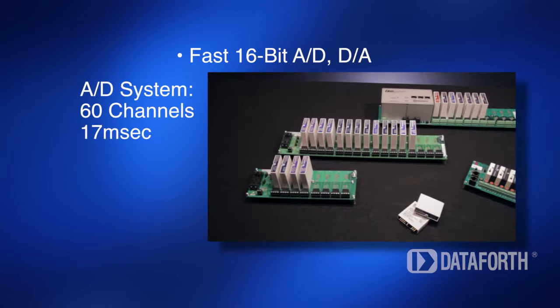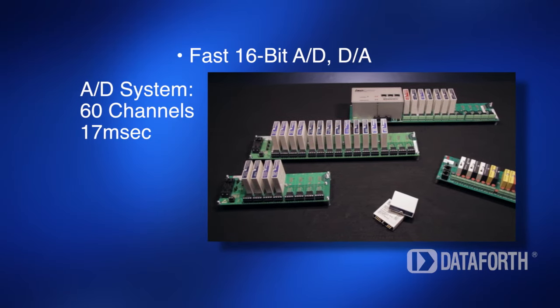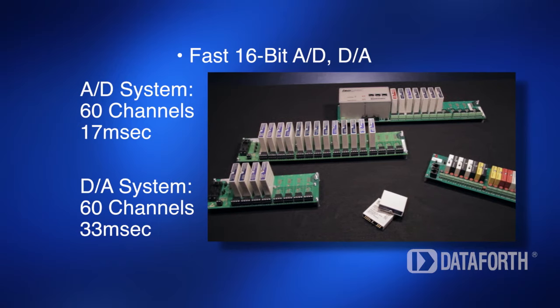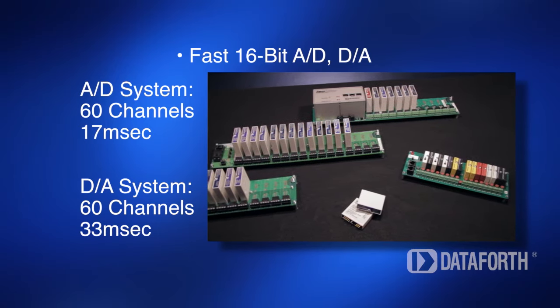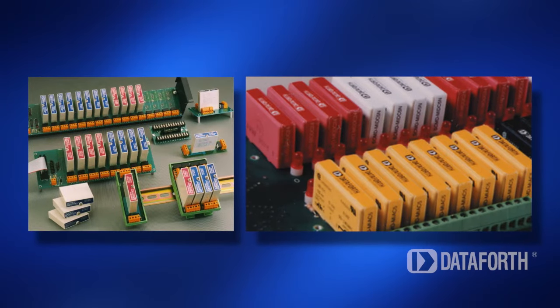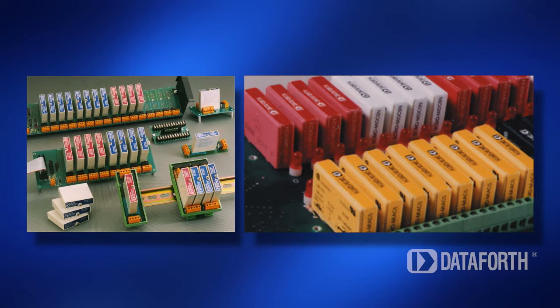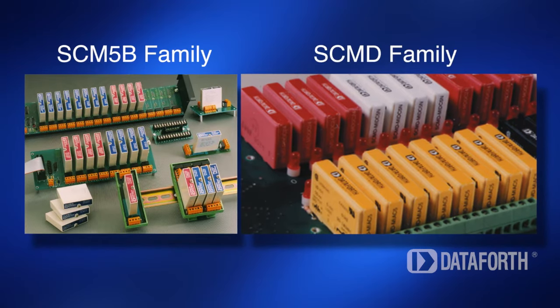The analog-to-digital system can convert a maximum 60-channel configuration in 17 milliseconds. The digital-to-analog converter can write a 60-channel configuration in 33 milliseconds. The signal conditioners used to build an optimal SLX200 system, tailored to a specific application, are Dataforth SCM5B analog and SCMD discrete I/O modules.